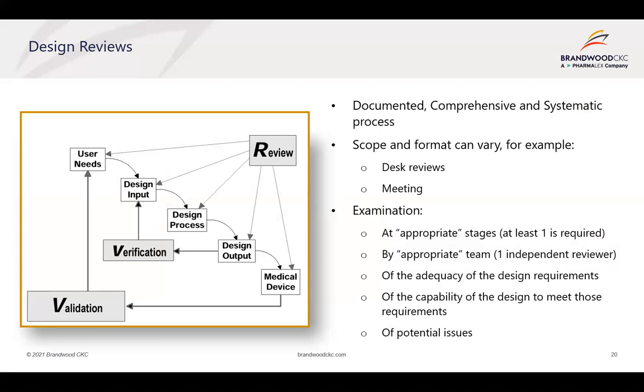As with many other components of the quality management system, independence and objectivity are very important to make sure the output is effective. You must involve someone independent from the work being produced to critically evaluate the design phase. It's an examination of the adequacy of the design requirements, the capability of your design to meet those requirements, and a way to identify potential issues that need resolving prior to the design release phase.